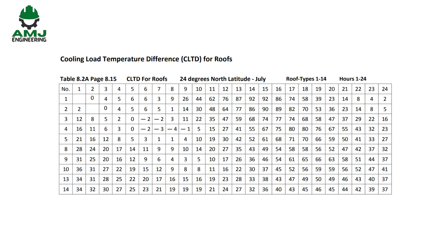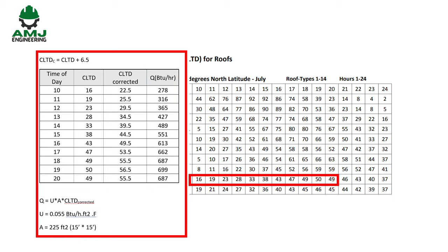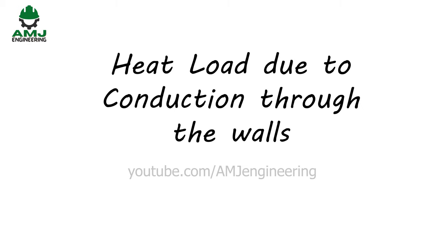I will do the load calculations from 10 a.m. to 8 p.m. because the peak load will occur within this range. After calculating CLTD_corrected, the heat gain through the roof at different hours is easily calculated on an Excel sheet using Q = U × Area × CLTD_corrected, with the roof area considered for one room.